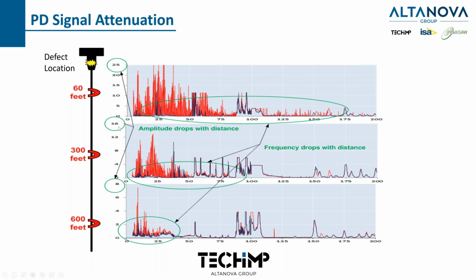Amplitude drops to 16, and as you can see, the bandwidth has dropped. And then we go to 600 feet. Again, amplitude has dropped to 8, and you see the frequency bandwidth has dropped a lot. So what that tells us is we're moving away from the defect. The person analyzing the data says, hey, wait a minute, we've got the partial discharge, and this is where it's at.